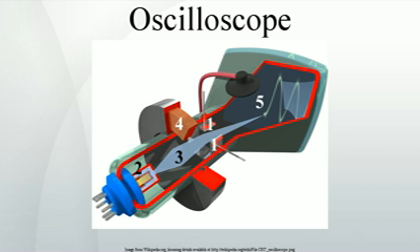Astigmatism. Can also be called shape, or spot shape. Adjusts the relative voltages on two of the CRT anodes such that a displayed spot changes from elliptical in one plane through a circular spot to an ellipse at 90 degrees to the first. This control may be absent from simpler oscilloscope designs or may even be an internal control. It is not necessary with flat panel displays.